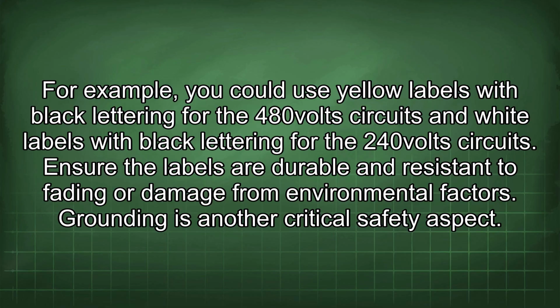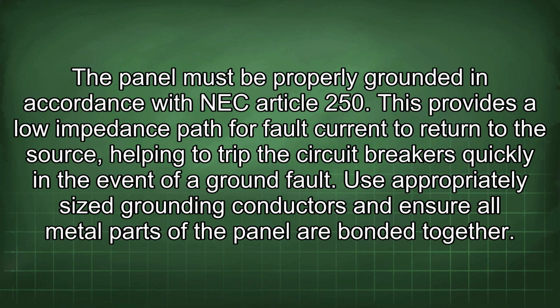Grounding is another critical safety aspect. The panel must be properly grounded in accordance with NEC Article 250. This provides a low impedance path for fault current to return to the source, helping to trip the circuit breakers quickly in the event of a ground fault.